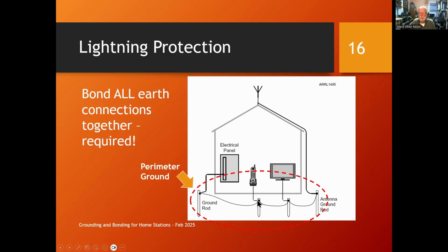Check your building codes. Number 6 is typically the smallest wire between all of your external ground electrodes. And the NEC is unequivocal on that. It says all external ground electrodes shall, S-H-A-L-L, be bonded together. And there is no wiggle room in shall. You absolutely have to do this outside. If you have more than one ground rod, get out there and bond them together. That's called your perimeter ground. Everything outside that's connected to the earth is bonded together.